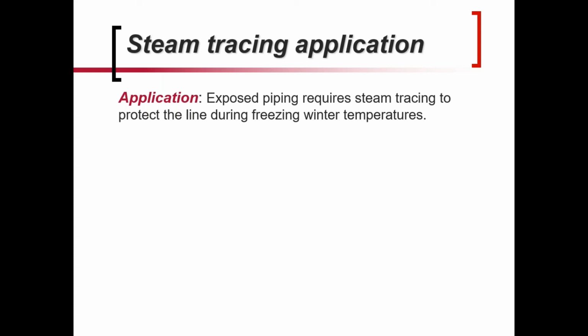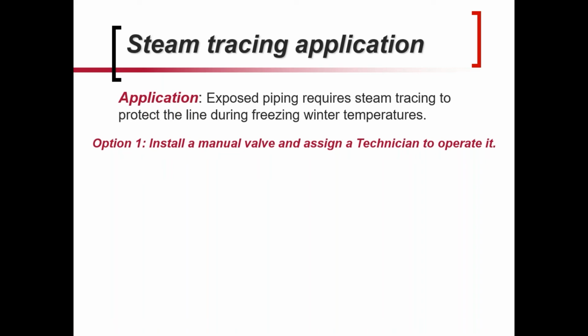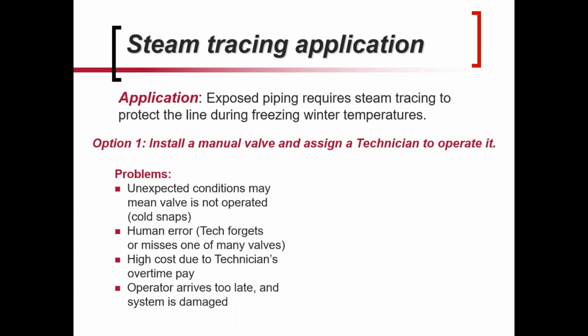But I wanted to talk about another application, which is steam tracing. Everybody knows what steam tracing is. So, a lot of facilities have exposed piping that needs steam tracing to protect lines, especially in the winter. And I'm just going to use water because it's so familiar and everybody gets that. So anytime the water gets below 32, there's a chance that your water lines are going to have issues. So a couple different ways to do this. You could install a manual valve on the steam tracing and assign a technician to operate it, which happens a lot. A couple of problems that can come up though.